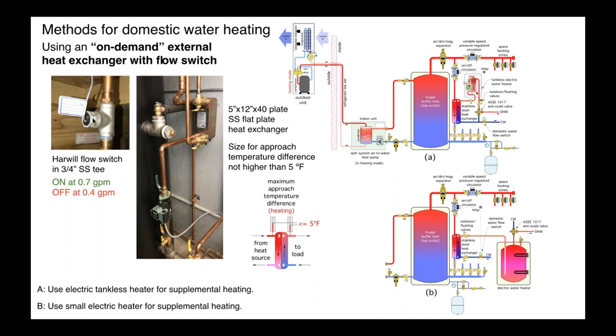So we've wired this over to a zone control panel, and that output on the zone control panel turns on the circulator. And so whenever there is a demand of 0.7 GPM or higher, open a faucet, turn on a shower, fill a bathtub, whatever it is, we're getting a preheating effect. We're basically taking hot water from the buffer tank, sending it through the primary side, and then picking up that heat. And again, we can boost it.